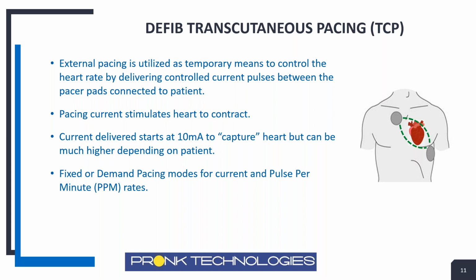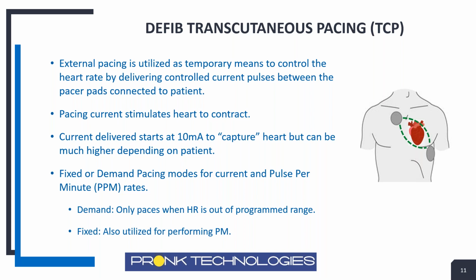And of course, the user can also control the pulse rate, so to speak, the pulses per minute, which will dictate the heart rate on the patient. So demand mode only paces when the heart rate is out of the program range. That can be used in the field on patients. Fixed can also be utilized, as I mentioned, and fixed is what we utilize when we're doing service on the units, when we're doing the PMs.